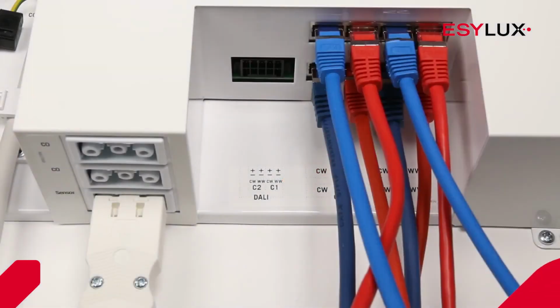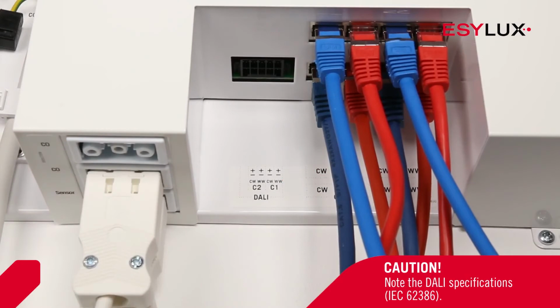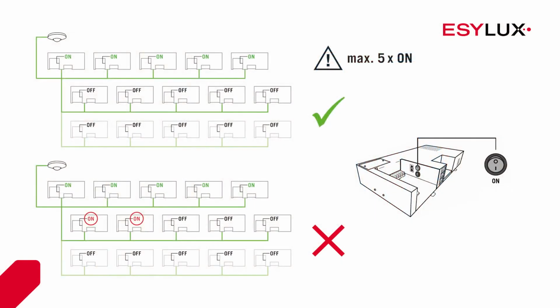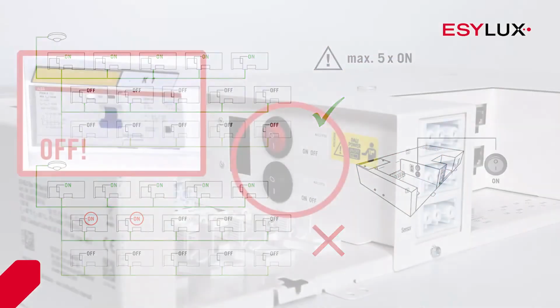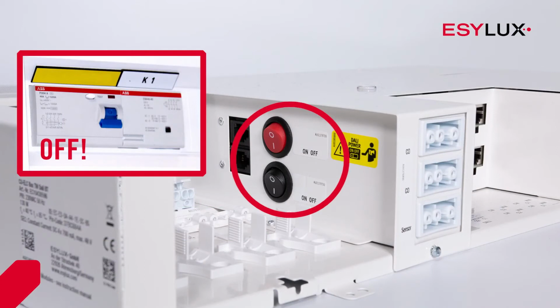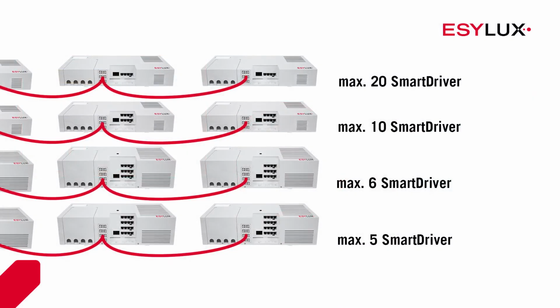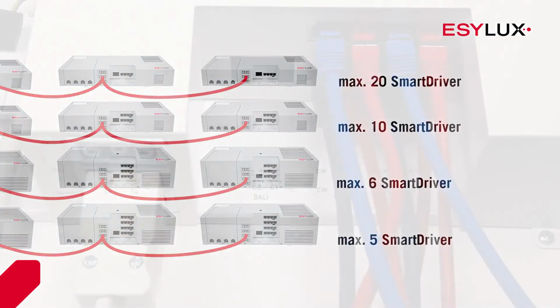If several SmartDrivers are connected to each other via the C0 interface, only a maximum of 5 SmartDrivers may have an active Dali power supply. Otherwise, this will damage the device. Please note that changes to the switches will only take effect once the supply voltage has been interrupted. The number of SmartDrivers which can be networked together depends on the variant.